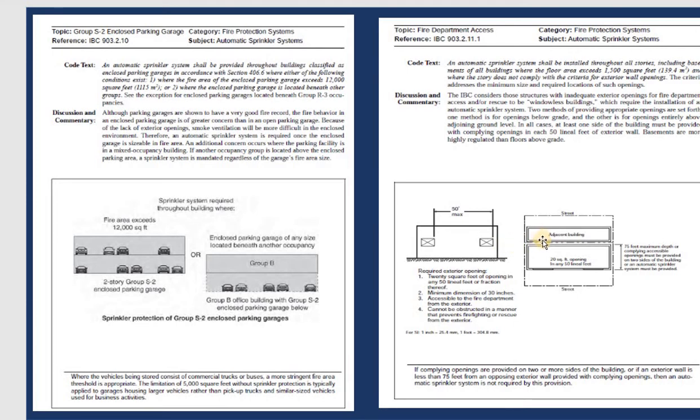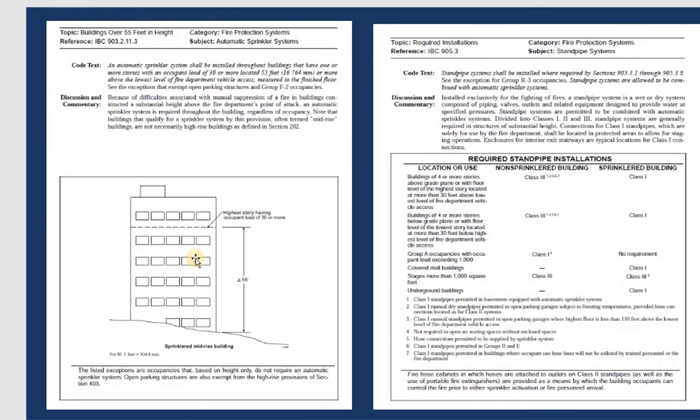And for the building, sorry, we have 20 square feet for the opening right here, and after that we have another building adjacent. For example, this is the floor plan, and the other one right here. So the maximum they allow is 75 feet for the maximum depth to comply if you use a non-sprinkler system. Okay, so more about that.